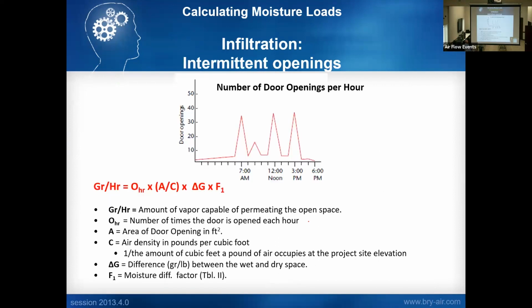Door openings, again, how many times people come in and out of doors per hour affects the moisture. You can see, moisture is going to spike whenever you have a door opening, so you got to account for it in your calculations. Typically what we do for sizing purpose, if we don't know, if you got 10 people in a space, we're going to assume about 10 door openings per hour, unless someone tells us different. Again, the drier you want to go with the room condition, the more you want to control in and out of people into that space.